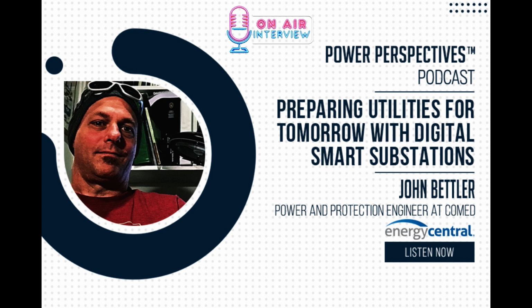So you're going to go to GIS gear, which is gas insulated switchgear. You're putting in everything new and cutting over to this new substation, versus a brownfield. Like we did a brownfield where we took one bus out and upgraded it, and the whole rest of the station stayed older electromechanical relays, and it was even on a different voltage level. That would be a brownfield.